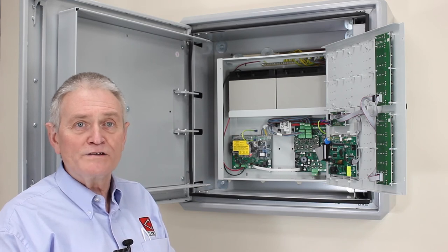As I mentioned earlier, the fact that an evacuation alert system is a system of last resort has implications for the wiring. The wiring in each flat needs to be separated from the addressable loop by an isolation device that protects against open and short circuit faults that may be caused as fire spreads through the building. In this way any number of faults in different flats can be present at the same time without affecting any other flats.